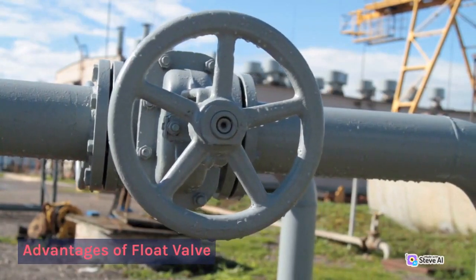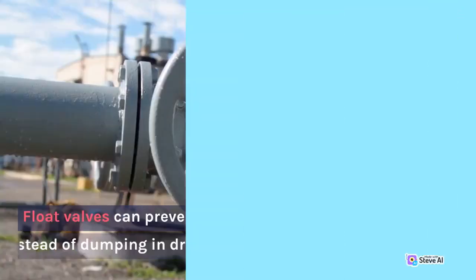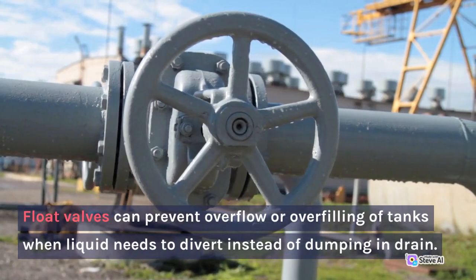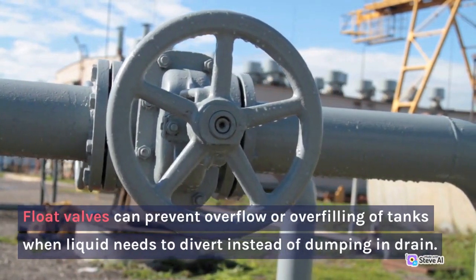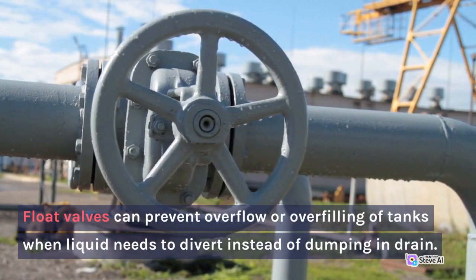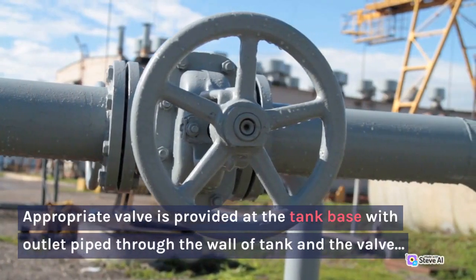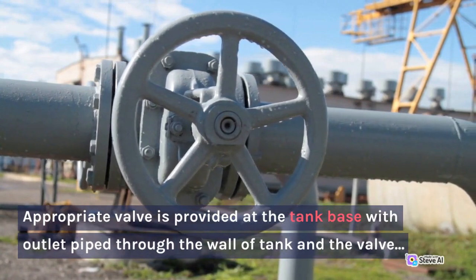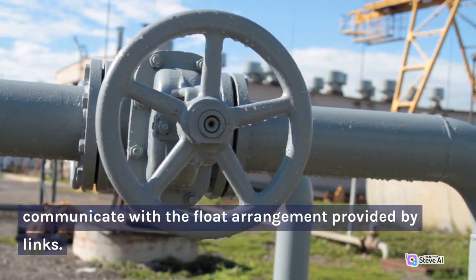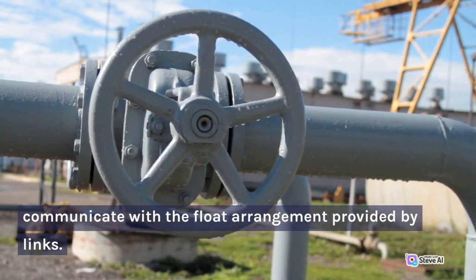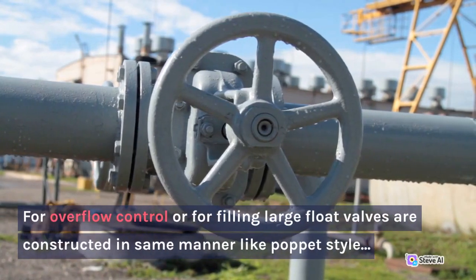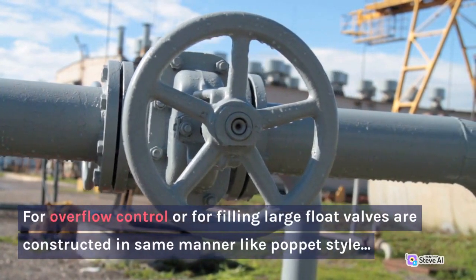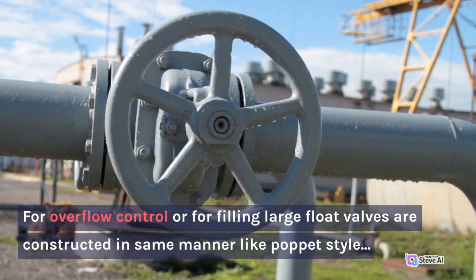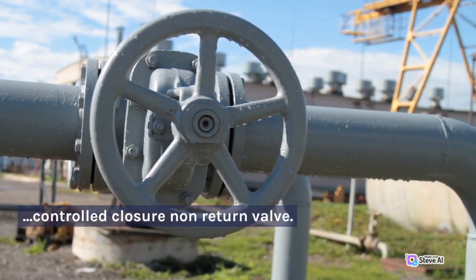Advantages of float valve. Float valves can prevent overflow or overfilling of tanks when liquid needs to be diverted instead of dumped and drained. An appropriate valve is provided at the tank base with an outlet pipe through the wall of the tank, and the valve communicates with the float arrangement provided by links. For overflow control or for filling, large float valves are constructed in the same manner as a poppet style controlled closure non-return valve.